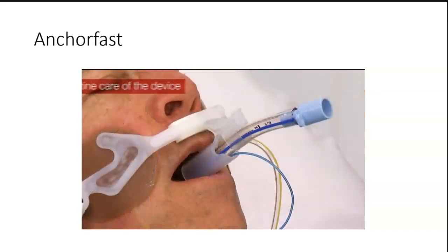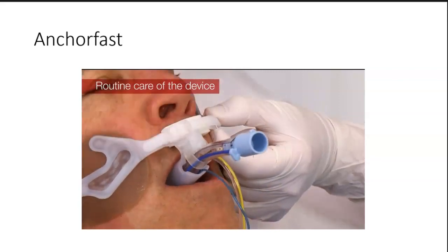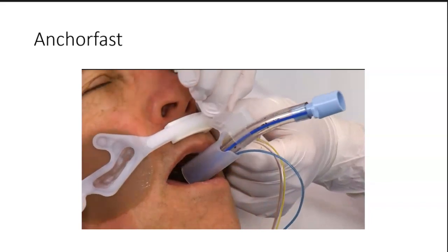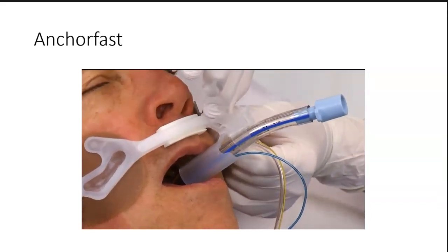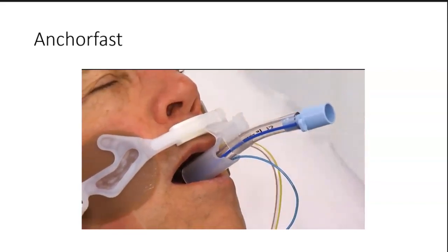To reposition the ET tube, squeeze the gliding tube shuttle tabs on the outer edges and move in either direction along the track. Reposition the ET tube from side to side at least every 2 hours, or more frequently if the patient's condition dictates, to minimize the risk of injury to the skin, lips, and/or oral cavity from unrelieved pressure and shear forces.